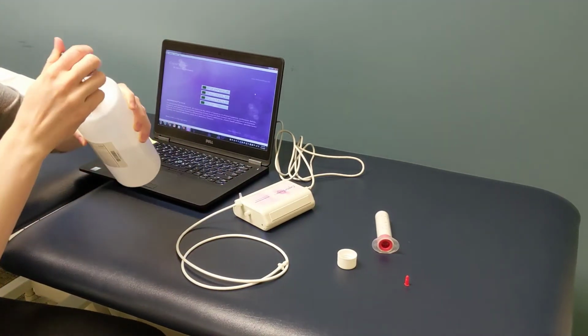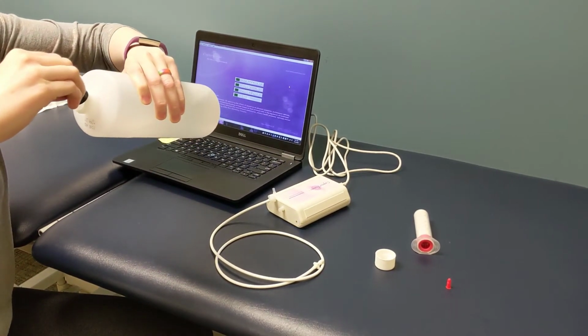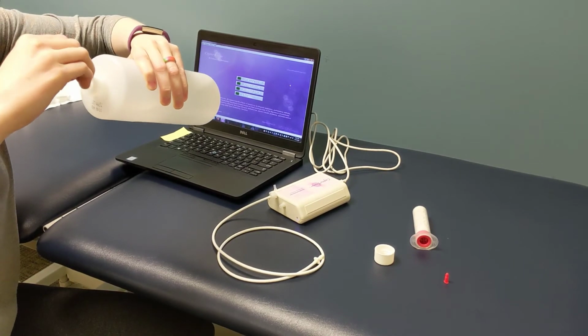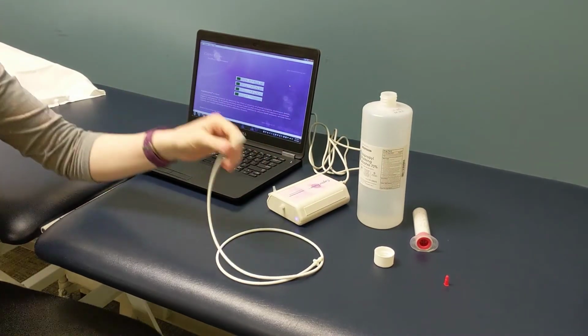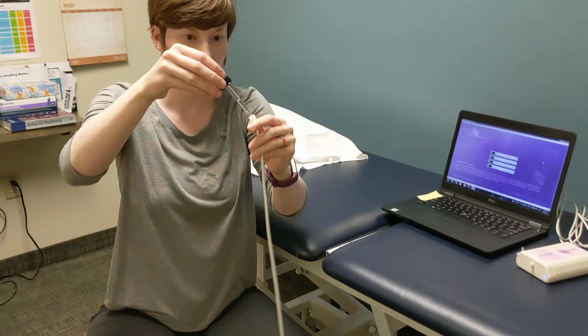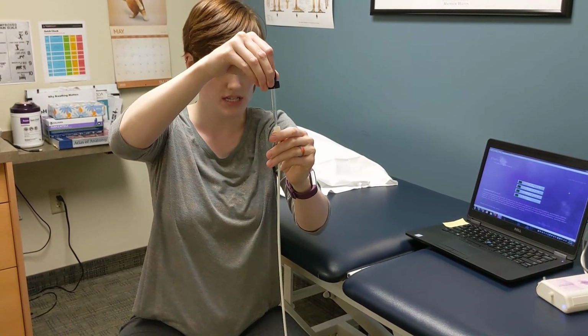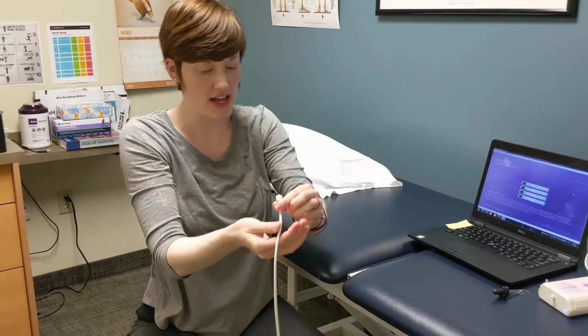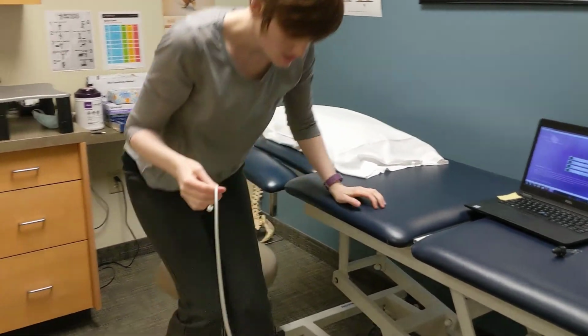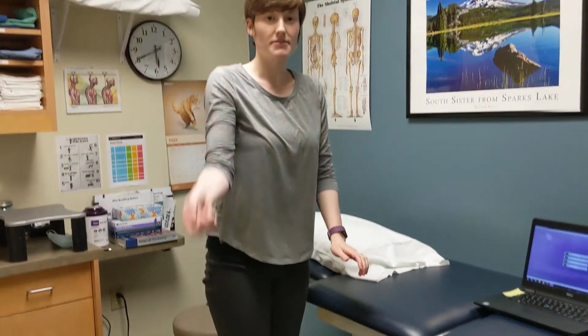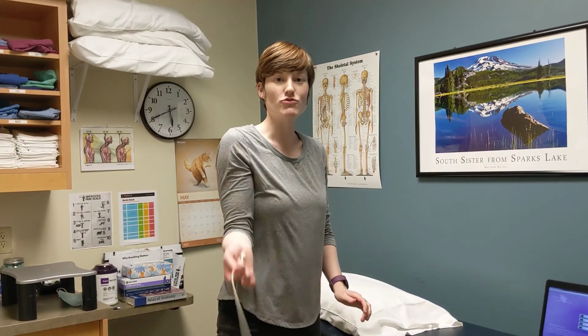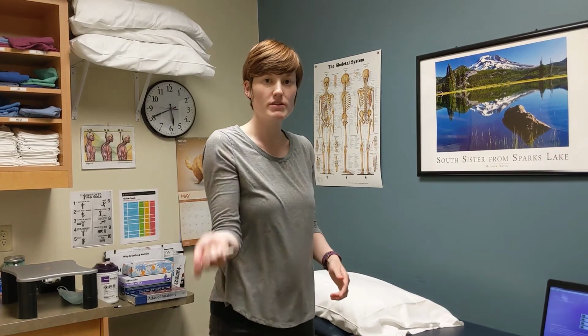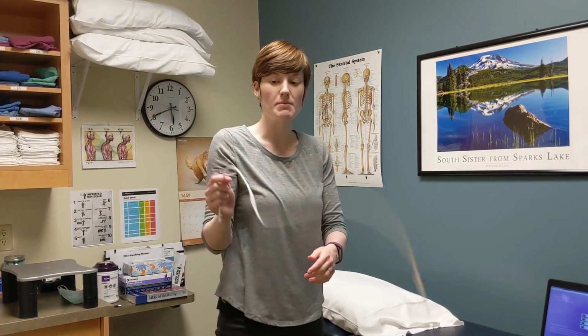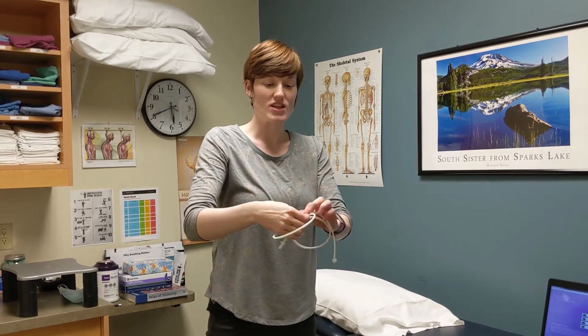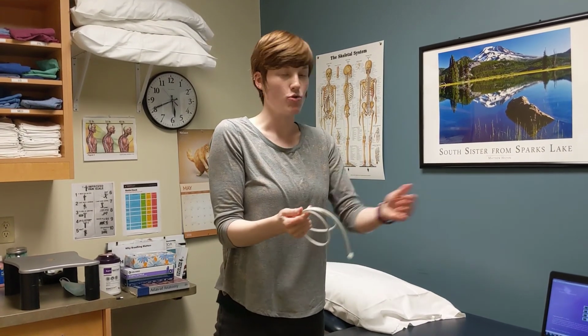To clean out the sampling tube, you can take a pipette and some isopropyl alcohol, and send it through the sampling tube. And then you're going to want to get out any excess water or the alcohol by spinning it around. And you'll do it from both ends. Then you're going to want to let that dry. So if you use this very frequently with clients, you're going to want to make sure you have a couple extra sampling tubes just so that this one has the opportunity to dry before you use it again.